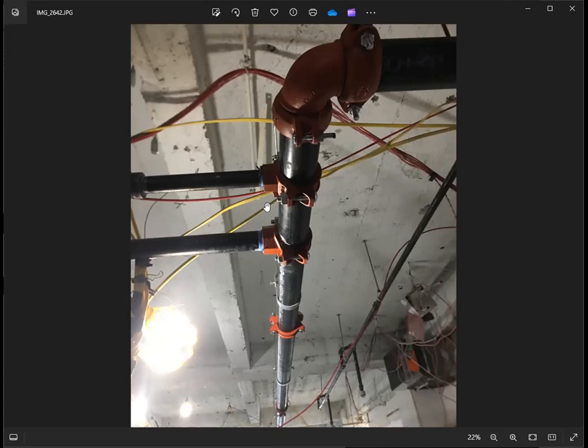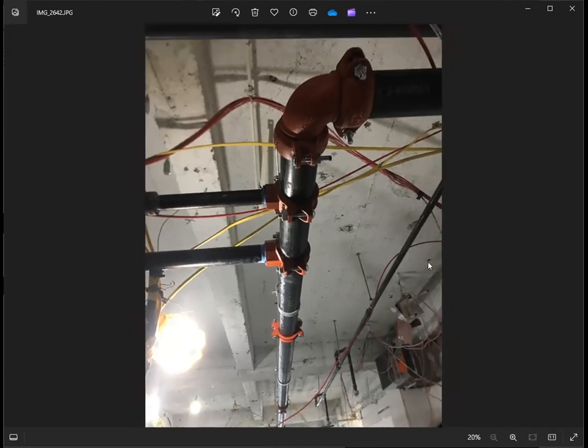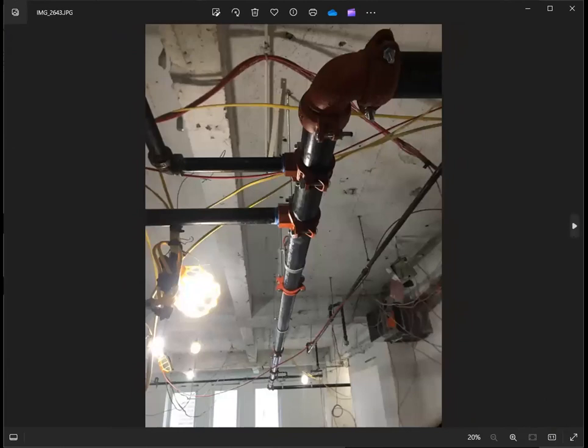So as an inspector, it's your duty to tell them that the test is not holding or it has some leaks. It should be fixed first before you do the test again. Because with some pressure gauges, you don't know, these are mechanical gauges, it might be broken or something. So most importantly, you should not have any visible leaks on the whole installation of the pipe.